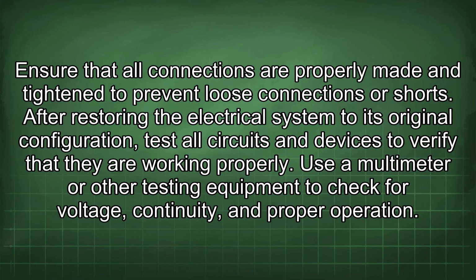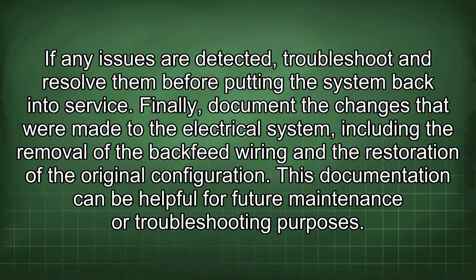After restoring the electrical system to its original configuration, test all circuits and devices to verify that they are working properly. Use a multimeter or other testing equipment to check for voltage, continuity, and proper operation. If any issues are detected, troubleshoot and resolve them before putting the system back into service.